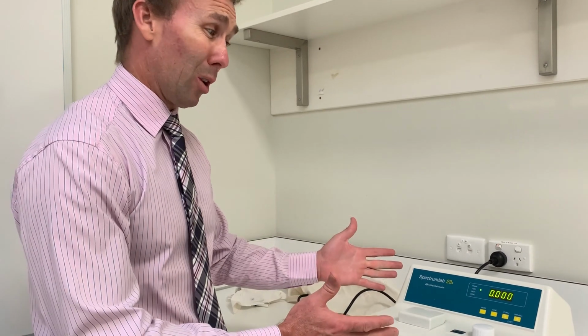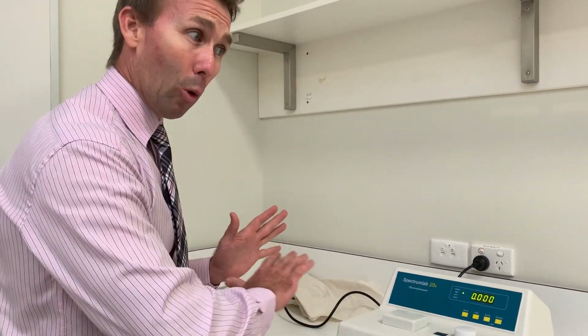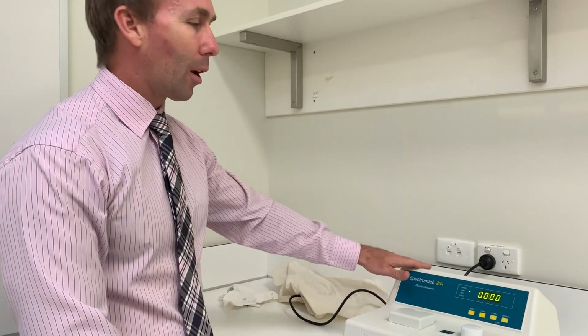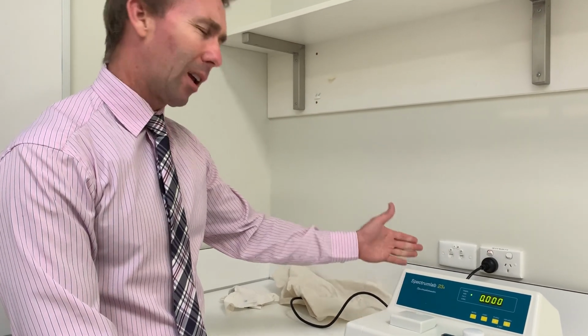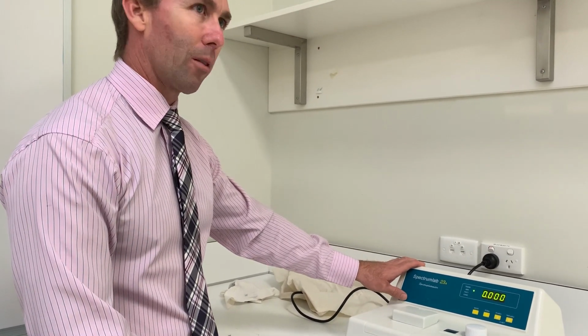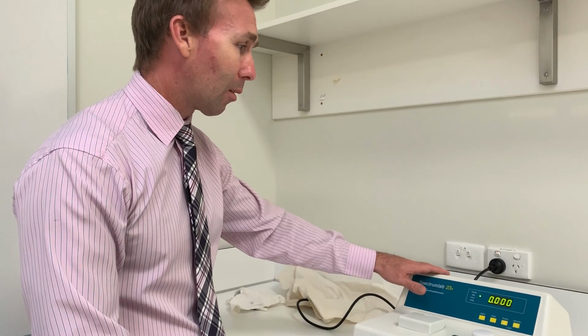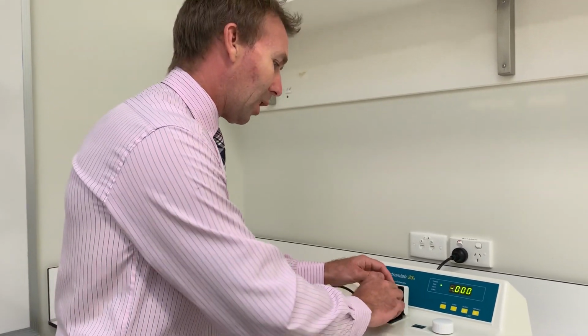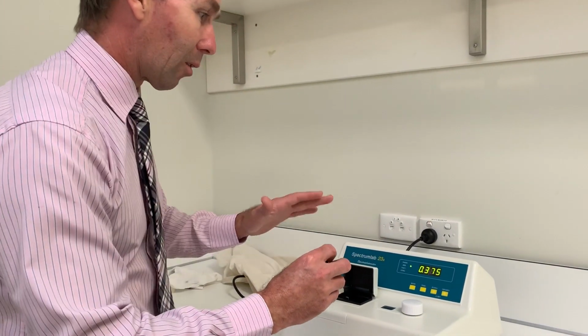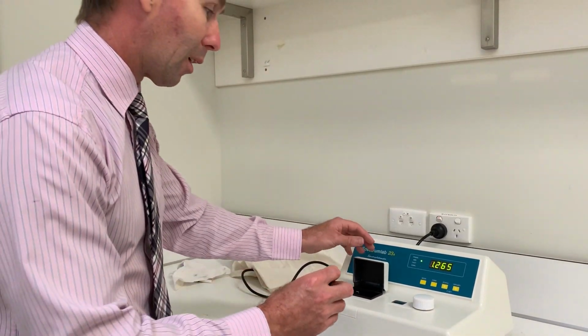My hint on these machines would be to keep putting in your blank. In theory, you only have to put your blank in once, press 100% adjust, and it will hold through all your samples. But I know for a fact that these machines will drift. They're getting a bit old now. They've had some hard life over the last few years, so make sure that you keep putting your blank in every now and again and just keep zeroing it, or even between every sample.